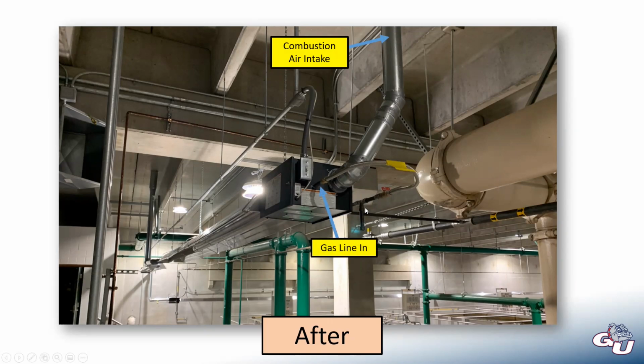Quick side note on the design: this little T here on the bottom is called a sediment trap, also known as a dirt leg. Anytime you have gas-fired equipment, you're supposed to have a capped-off T like that to collect any dirt that could have been carried along with the natural gas, because natural gas isn't completely clean as it gets to your building.